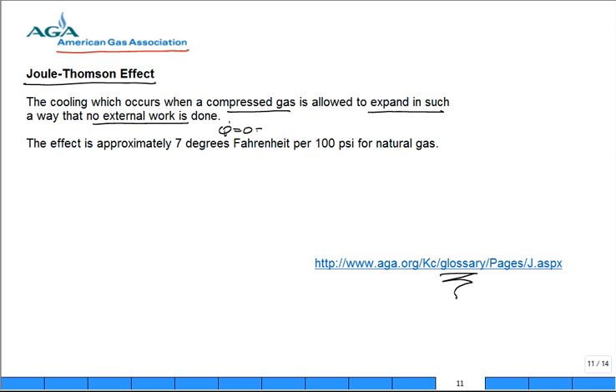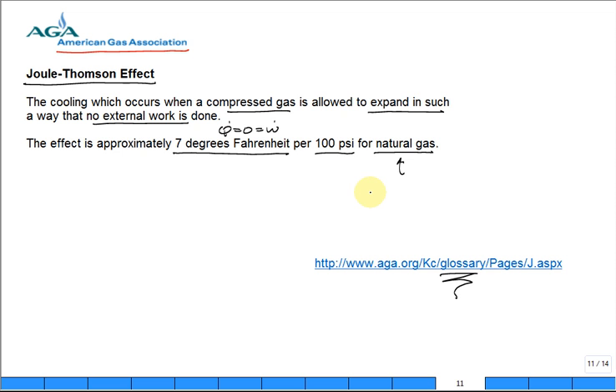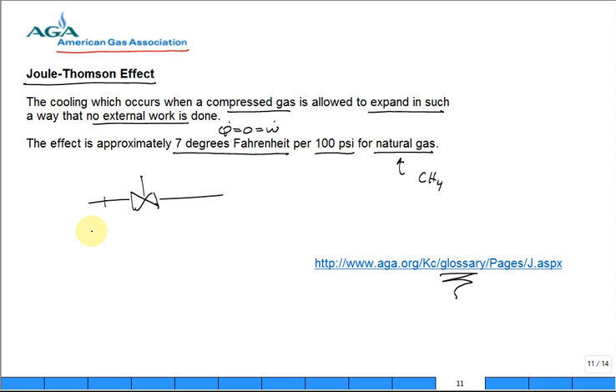They say the effect is approximately seven degrees Fahrenheit per 100 psi for natural gas. What is natural gas primarily? Methane, CH4. So if you have a pipeline of methane, then you have a valve and that valve is partially closed, it's a restriction.